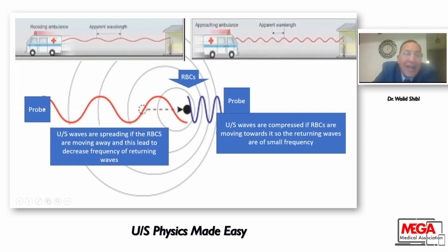By means of spread, that means there is a decrease in frequency. So the frequency coming from the probe, which is the emitted frequency, is more than the reflected frequency from the moving away red blood cell. And this is the frequency shift, the difference between the reflected frequency and the emitted frequency. As you see, if the reflected frequency is less than the emitted frequency, the spectral Doppler will appear below the baseline. Okay? But if the probe is here, and this is the emitted frequency, and the red blood cell is coming towards the probe, this will lead to condensation of the waves, and this means an increase in the frequency. So the reflected frequency will be higher than the emitted frequency, and this is the frequency shift.